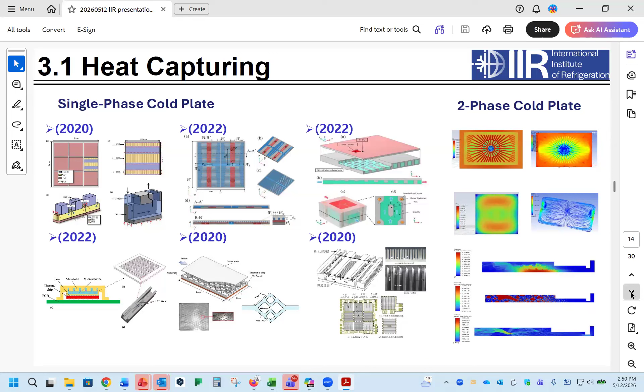This is for immersion liquid cooling. In cold plate liquid cooling, there is usually a mixed cooling system, where only the CPU and GPU are cooled by the cold plate, and other components are cooled by air. This system usually uses two kinds of cold sources: one for liquid cooling, where temperature can be high, and another for air cooling, which needs a lower temperature cold source, usually about 20 degrees or so.